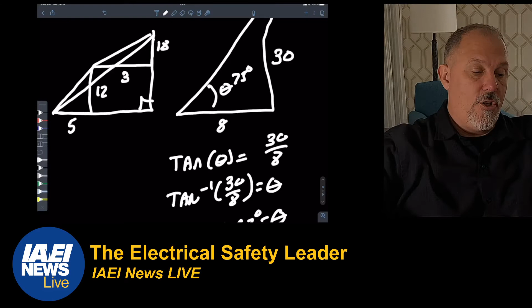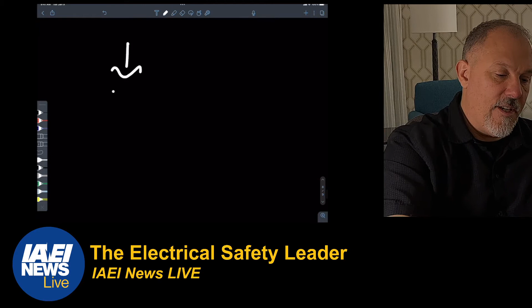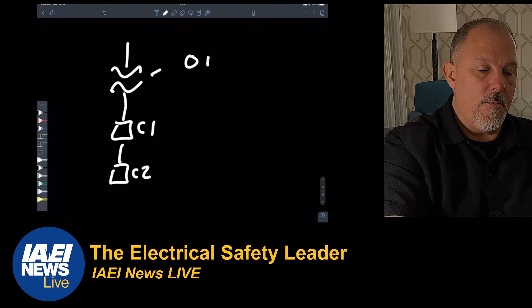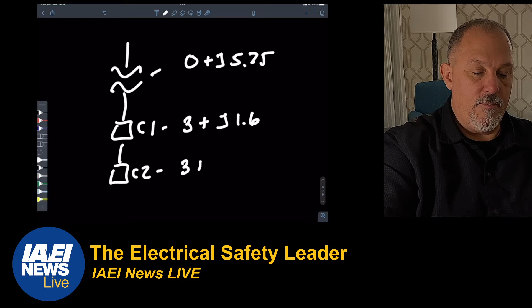So if I want to add lengths of conductors, different types, to add impedances in series with each other, where would I use that? I have a transformer, a conductor 1, and a conductor 2. If the transformer is all reactive, say 0 plus J5.75, and conductor 1 is 3 plus J1.6, and conductor 2 is 3 plus J1.6 — we'll say they're two of the same conductors at the same length. I would just add those up. You get 6.